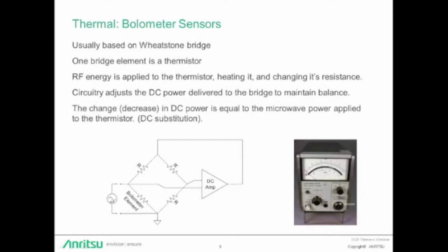To change, or actually decrease, to be more specific, in DC power, that change is equal to the microwave power applied to the thermistor. This relationship is called DC substitution. Also, you'll see today in most thermistor-based sensors, they'll have a second thermistor, which is set to compensate for ambient temperature changes.